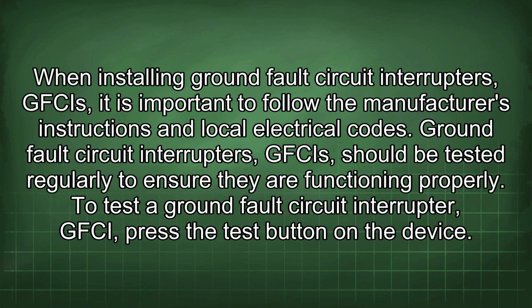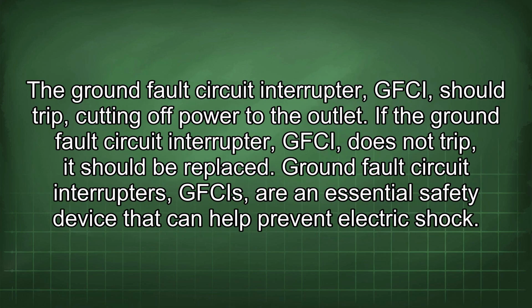When installing GFCIs, it is important to follow the manufacturer's instructions and local electrical codes. GFCIs should be tested regularly to ensure they are functioning properly. To test a GFCI, press the test button on the device. The GFCI should trip, cutting off power to the outlet. If the GFCI does not trip, it should be replaced.